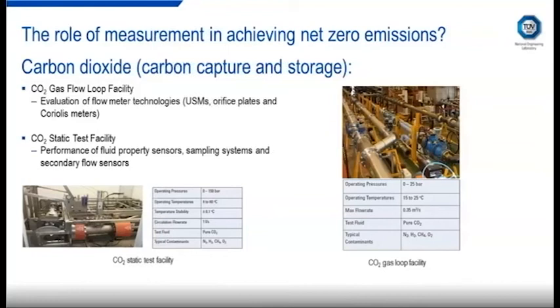We did some testing with CO2 in the gas phase, and it was actually mixtures of CO2 and nitrogen. So we tested in our wet gas flow facility, although there was no liquid present in these tests. And we tested in quite a large scale meters of 6 and 8 inch nominal bore. And we tested ultrasonic meters, Coriolis meters, and orifice plates. And we did that a number of years ago, actually, but we still have that capability now if it becomes of interest again.